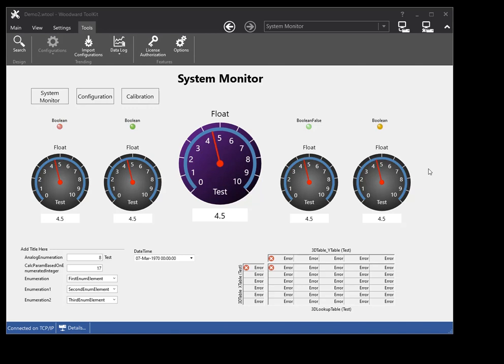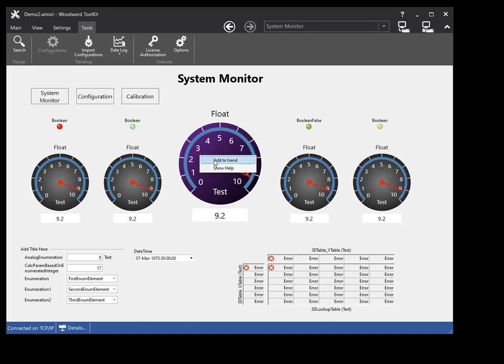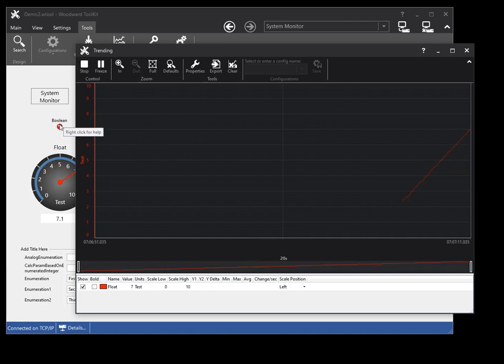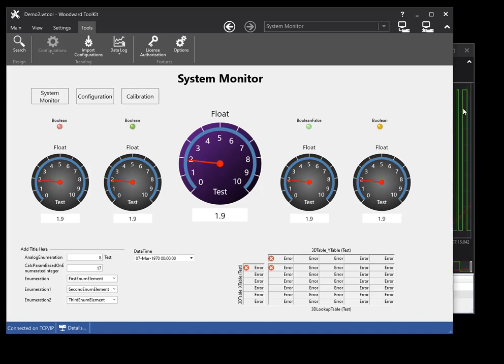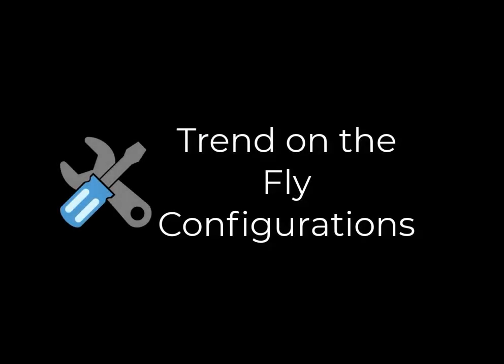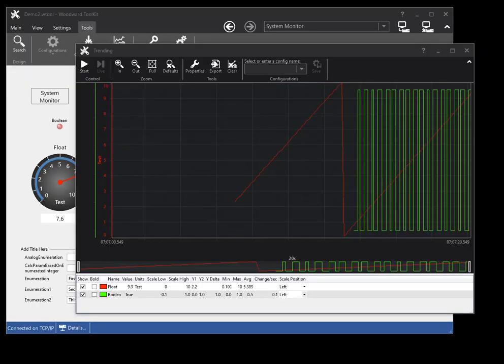Toolkit allows you to trend any parameter value even if a trend chart is not part of your tool. This feature is called trend on the fly. To trend on the fly, right-click on the component containing the parameter value you wish to trend, then left-click the Add to Trend pop-up menu item. The trending window will open with the parameter value you selected. Click the start button on the trend toolbar to start plotting data. To add additional parameters, repeat the steps with the components containing the parameters you wish to trend. Trend on the fly configurations can be saved in the tool user options file and restored at a later time. If you create a trend on the fly and don't save the changes in a configuration, the trend on the fly configuration will be lost when the window or tool is closed. Saving the trend on the fly configuration is done the same way as in an embedded trend chart.